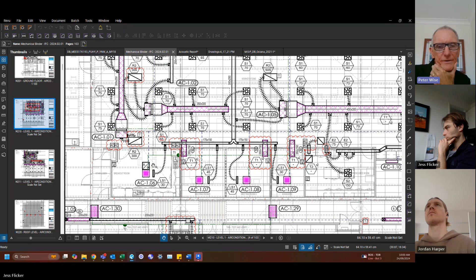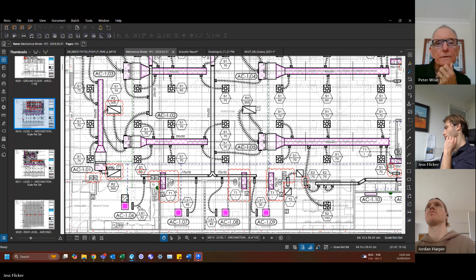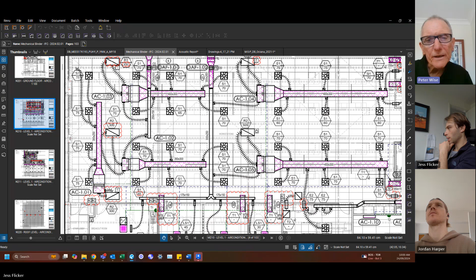It's probably okay, it's only a small fan, isn't it? Yeah, it's like 30 liters a second per room. What's the total? 150. So it's just an inline centrifugal type fan, with a fair bit of duct and some internal insulation. So I'd say it's going to be okay.